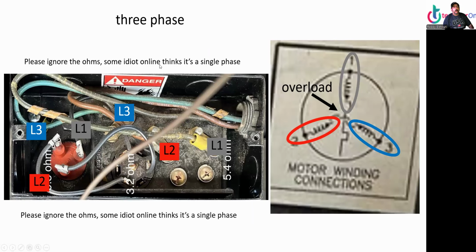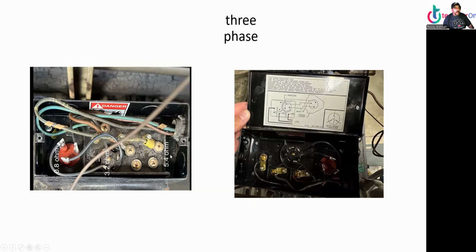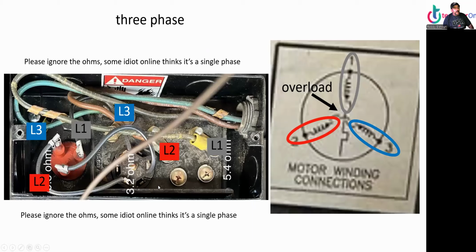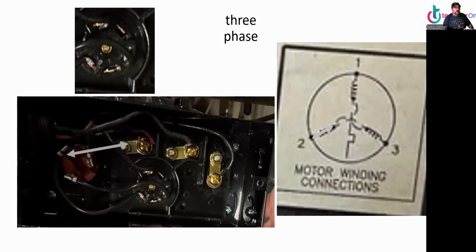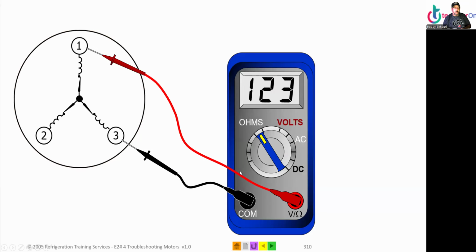Please ignore the ohms. Some idiot online thinks it's a single phase. Right, these numbers add up. 0.8, 3.2, 5.4. They add up, but if it's single phase, you can tell it's a three-phase by the overload. It's a three-phase overload. I mean, come on, man. So many idiots out there. All right, another example of three-phase. So now this is three-phase motor windings. Between this connection and this connection, that's one of the windings. Starts here, ends here. The other winding starts here, ends there. And the other winding, blue, starts here. They meet in the middle at the overload.